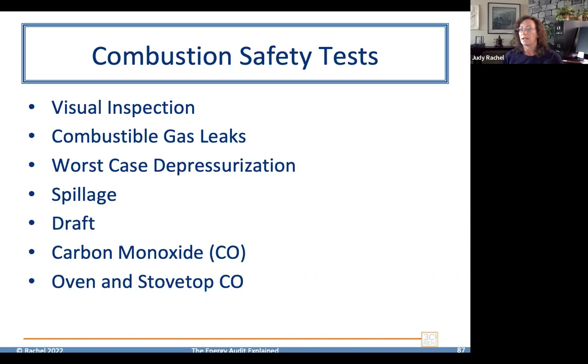And under worst case depressurization, we test for spillage, which is those combustion gases coming out of the vent instead of venting up through it, testing the actual draft, the pressure of the draft, to make sure that it's in a safe range, testing for the carbon monoxide that the combustion appliance is producing, versus what's also in the ambient air around the combustion appliance, and doing those carbon monoxide tests on the oven and stovetop as well.